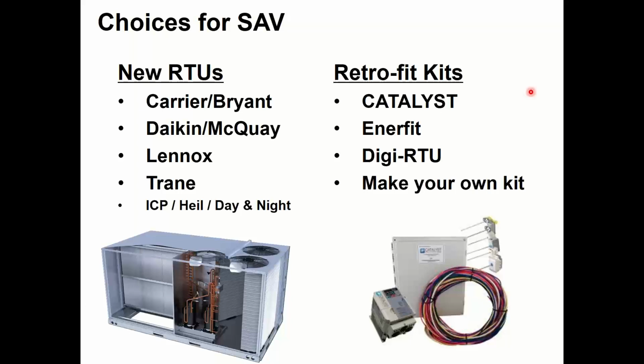As a general statement, what I'm going to tell you is if you have a rooftop unit that's 10, 12 years old, it's not worth investing money into enhancing it, because if you recall, the average life expectancy of your rooftop is only 15 years. I don't want to put $4,000 into my rooftop unit of enhancements that may only last me a few years. Now, can you make your unit last till it's 20, 25 years old? Yeah, sure you can, by doing all the right things and all the right maintenance. But generally, when I get above 10 years old, I probably don't want to spend money making my unit better, right? But if I'm at the point I might want to replace it, I'm going to buy a new rooftop anyway, and I'm already going to spend whatever, $9,000 to buy the new rooftop unit. Why not spend $10,000 and get the new unit that has the staged air volume in it, or whatever the extra price adder is, right?